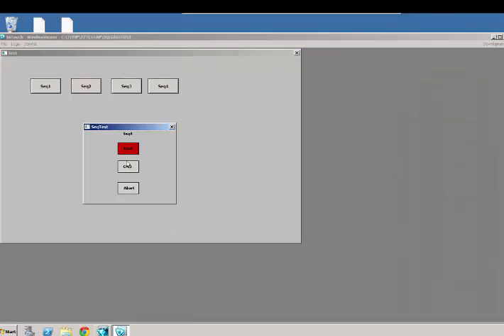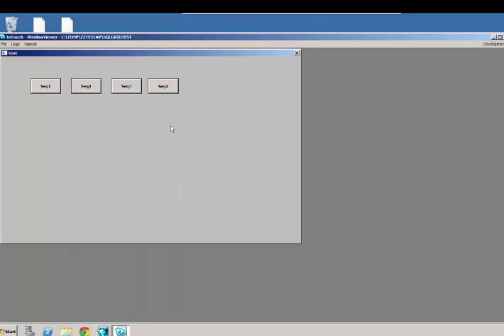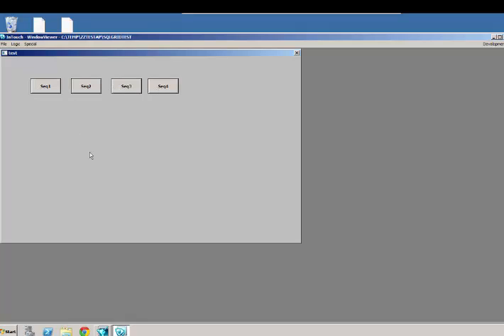and it's going to pop up the data for sequence number 4, and it's going to allow me to send some commands down to the PLC. So that's what the customer wanted to do. They wanted to be able to very quickly use one faceplate, this is a very simplified version of the faceplate he's going to use, it's going to have a lot more variables in it, but this is a little test scenario here that we put together to prove out that we can use the same tags, same three tags, and then based on the actual sequence number, the variable we're passing into it, change the address of the tags using the function of the SetIO function, right?